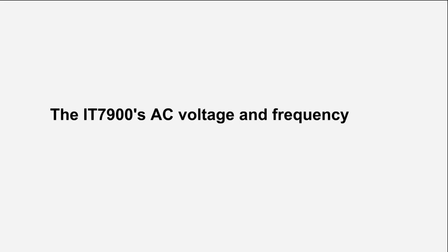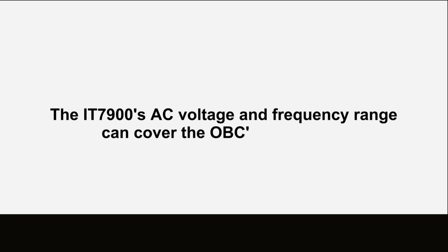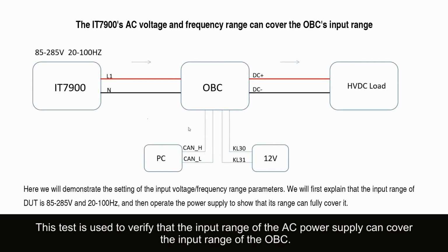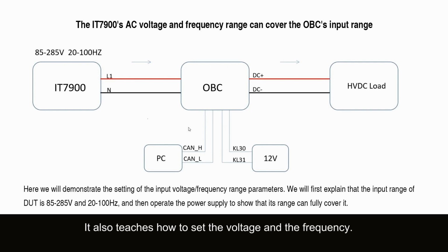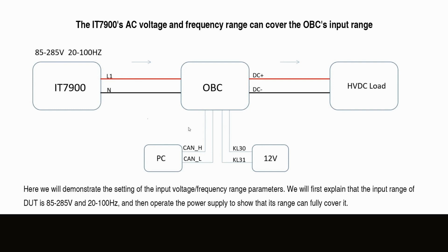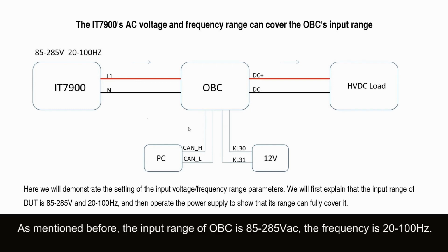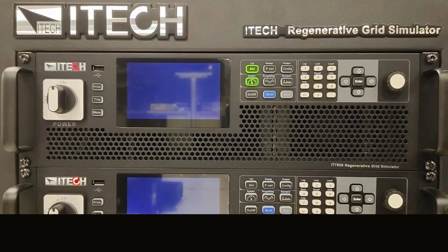The IT7900's AC voltage and frequency range can cover the OBC's input range. This test is used to verify that the input range of the AC power supply can cover the input range of the OBC. It also teaches how to set the voltage and the frequency. As mentioned before, the input range of OBC is 85-285 VAC, the frequency is 20-100Hz.